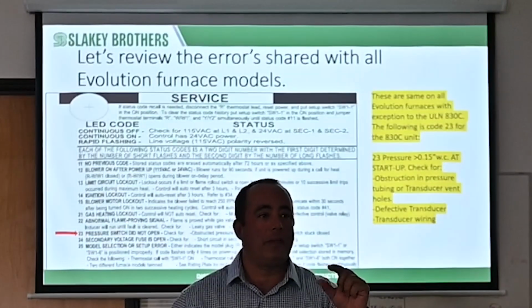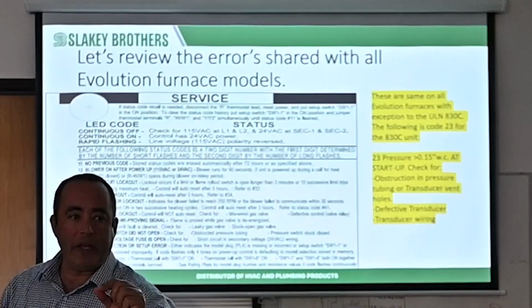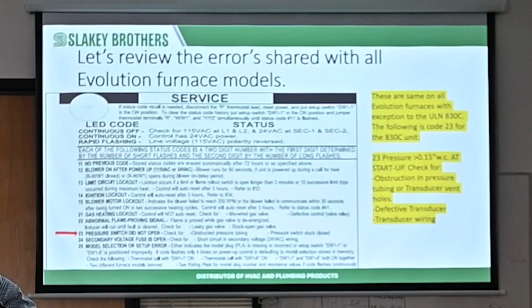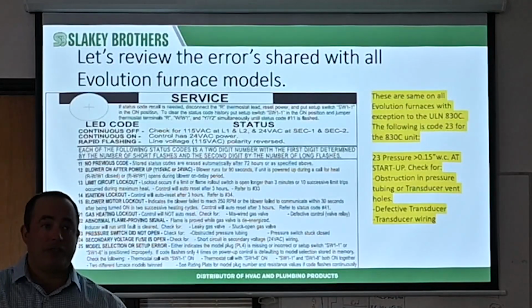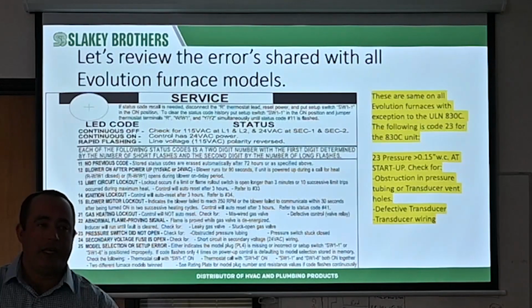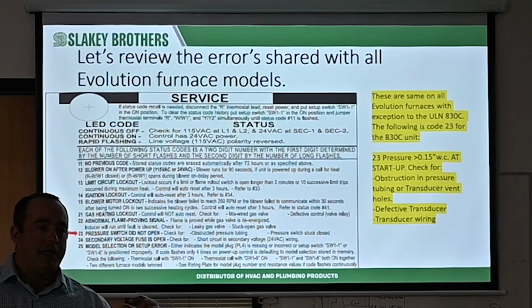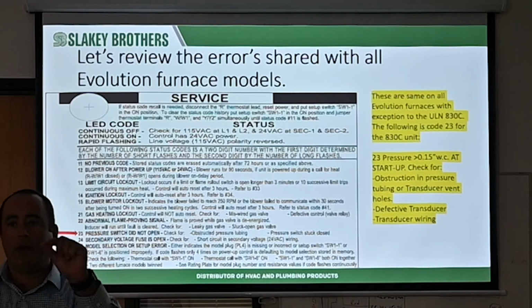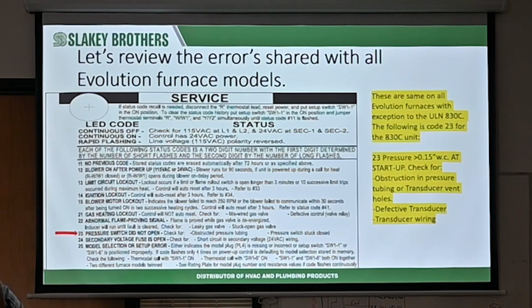It's like 3/4 inches by 3/4 inches. It's really, really easy to miss. For service work, guys have replaced the circuit board, put the new board in, and they get a 25 because they didn't take that little model chip from the old board and put it on the new one. On a brand new unit, if you get a 25, it's going to be for a couple of reasons, as you can see here in a second.